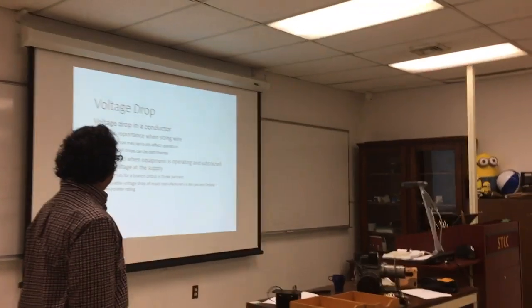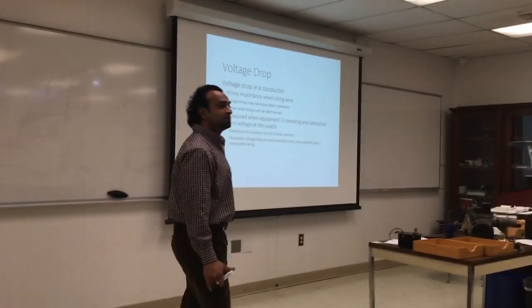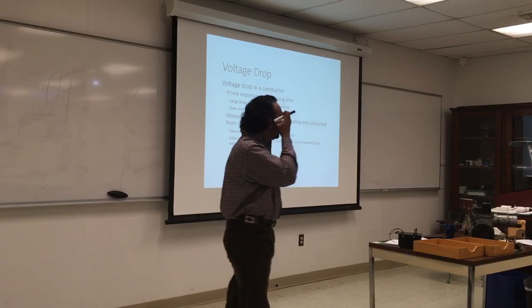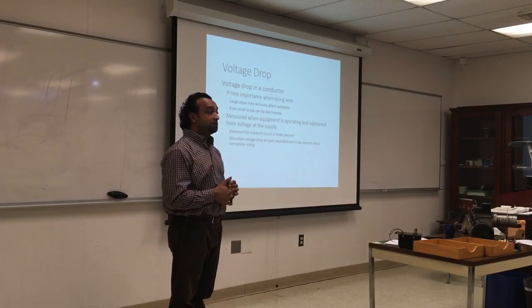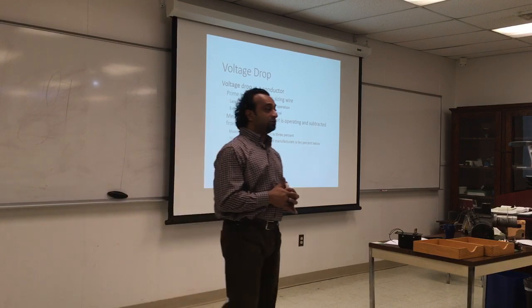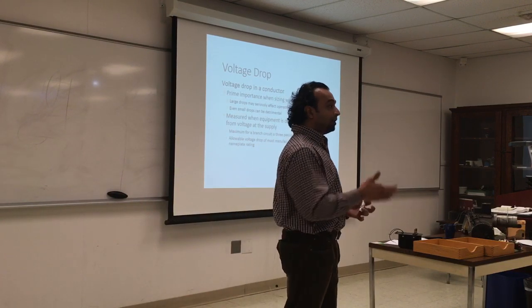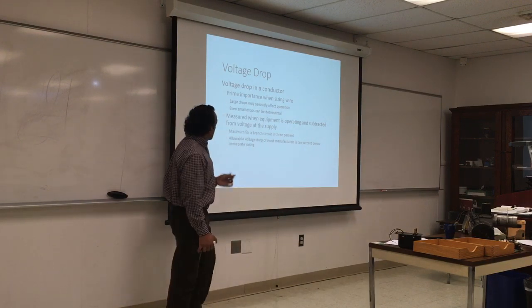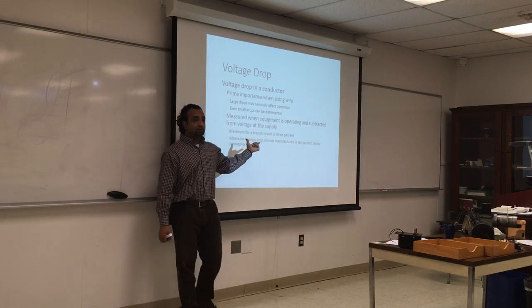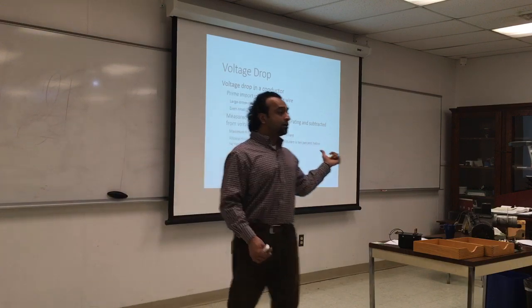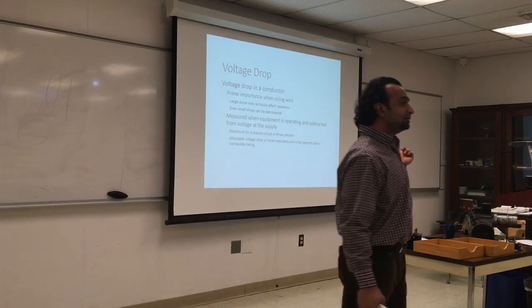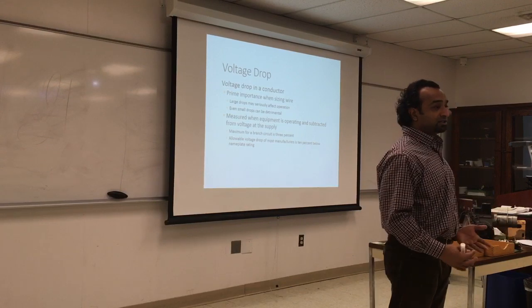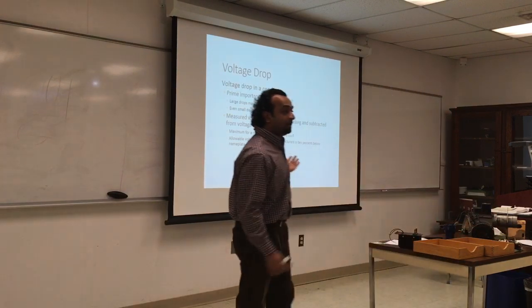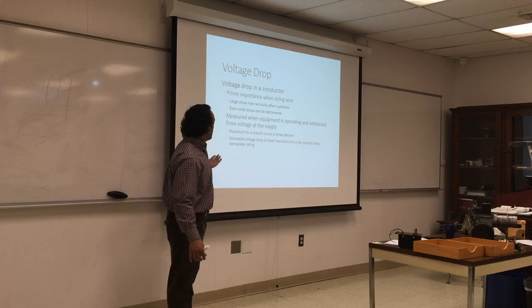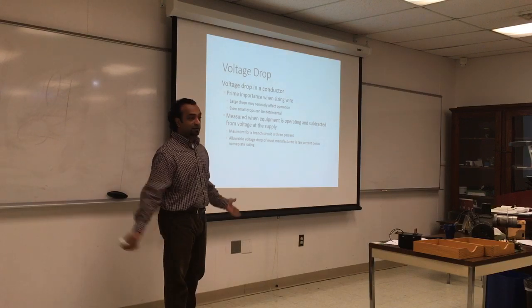Okay, so week 10, we're talking about sizing wires, and we're talking about voltage drop. And we said we always want the voltage to be within 10% above or below the nameplate. So the maximum for branch size, what is a branch? That's if you are connecting equipment in parallel, that's a branch. The drop for a branch is 3%. Yeah. For the main line, it should not be more than 10%.